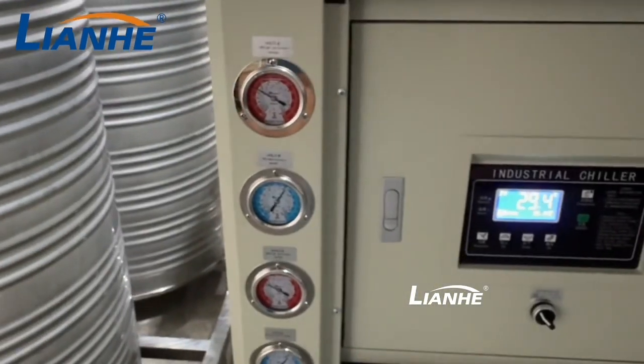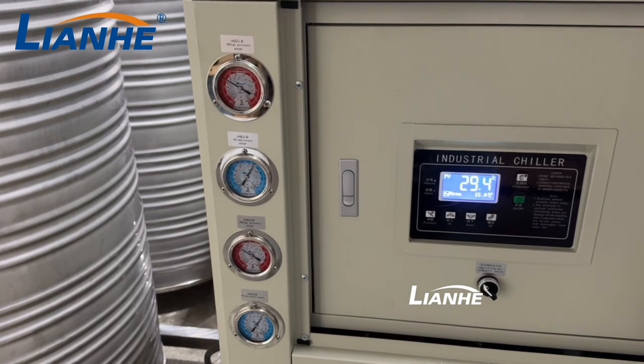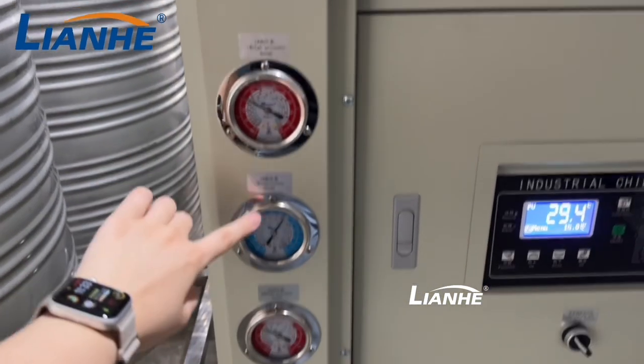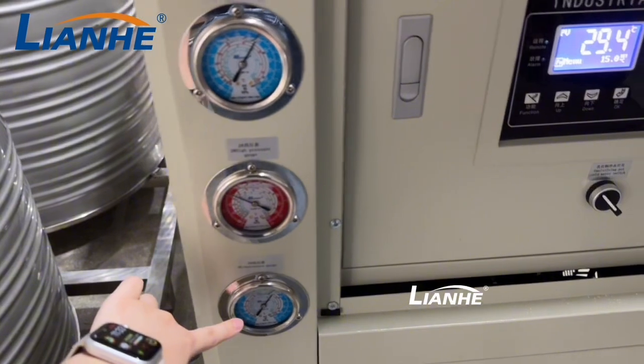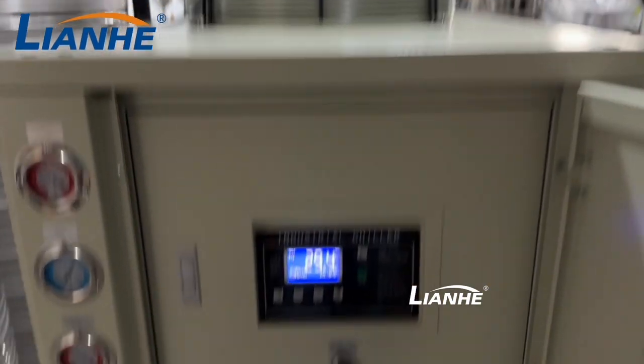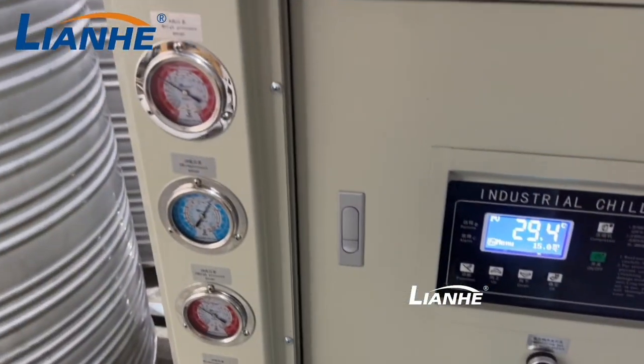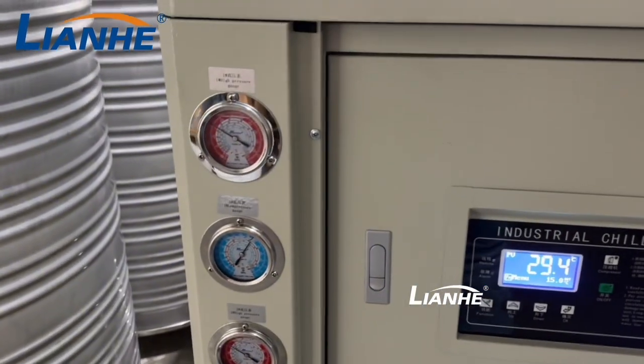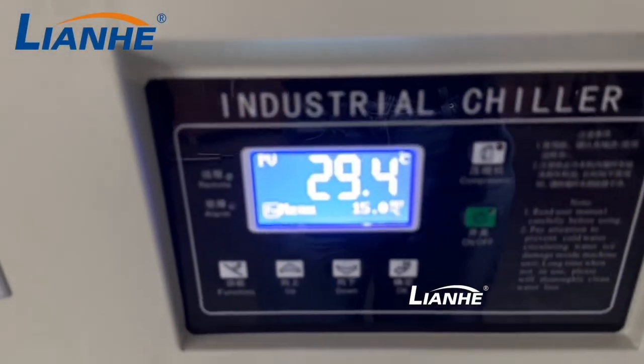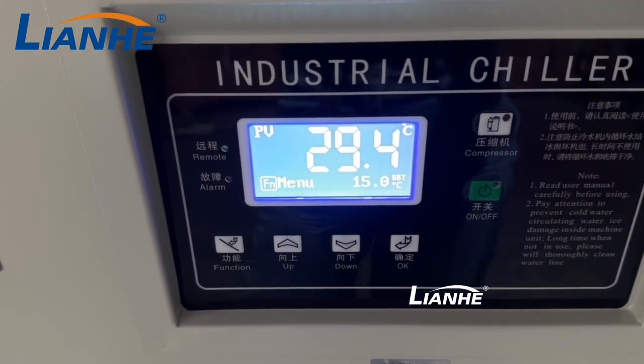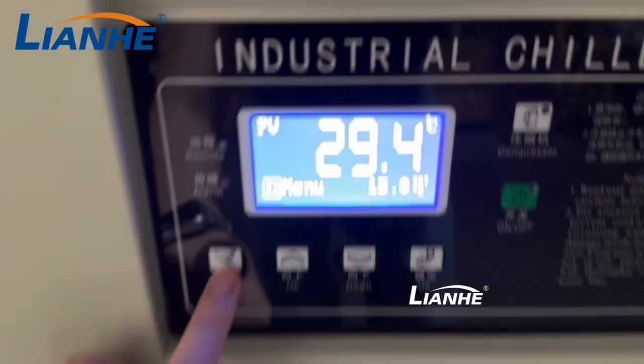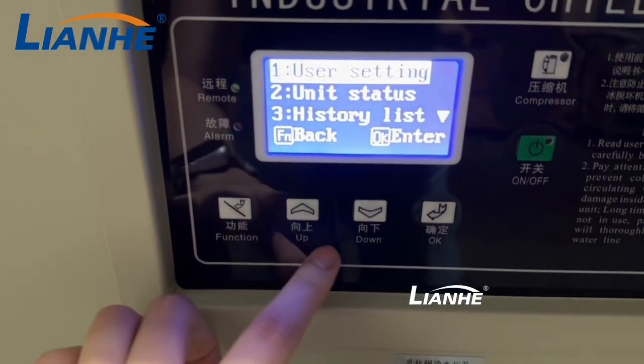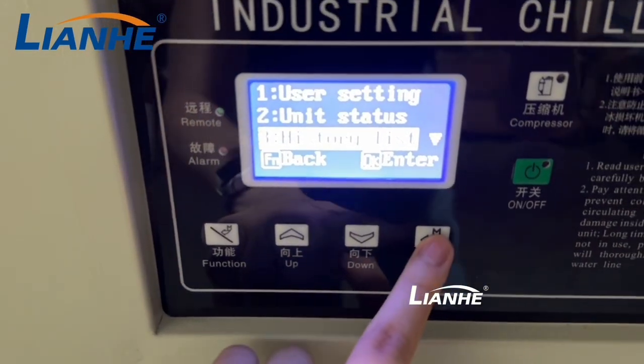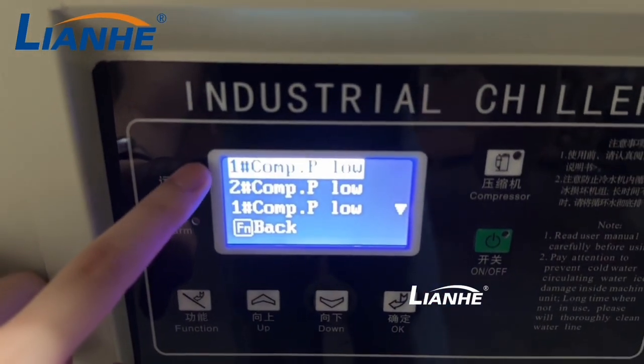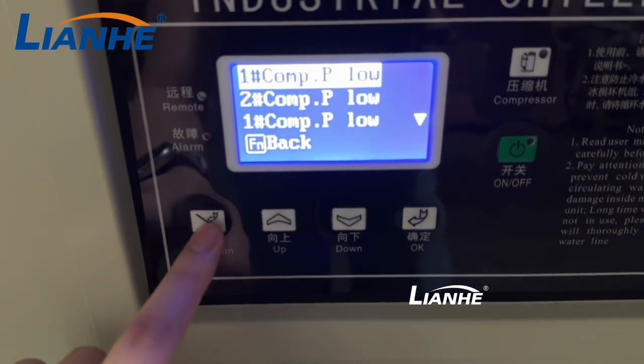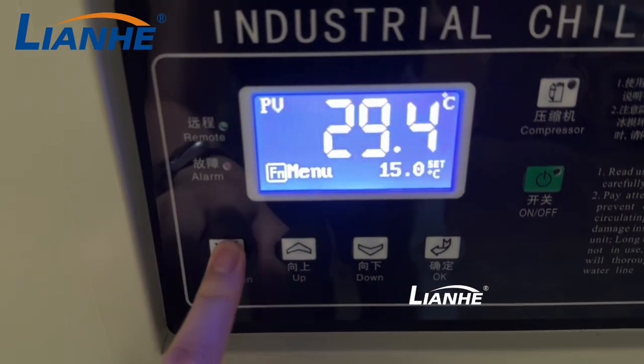And also, we equip you with 4 pressure gauges, the high pressure gauge and low pressure gauge of these 2 compressors. And when the pressure is higher or lower, the panel will display the high pressure alarm and low pressure alarm. Also, you can see here the menu. Take the function and go to the history list. It will show you the history alarms of the high pressure and low pressure, and you can get back to the function.